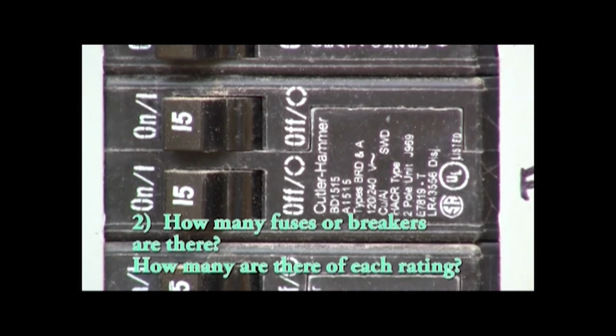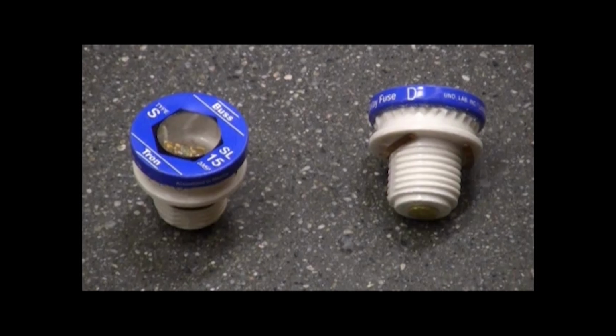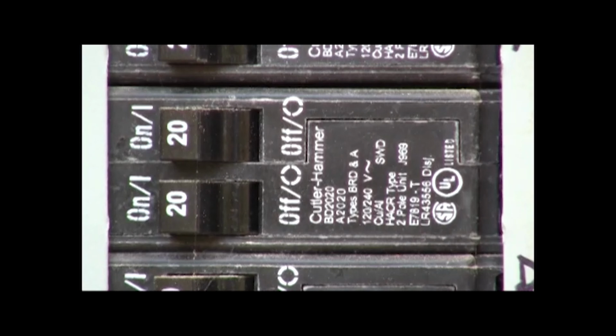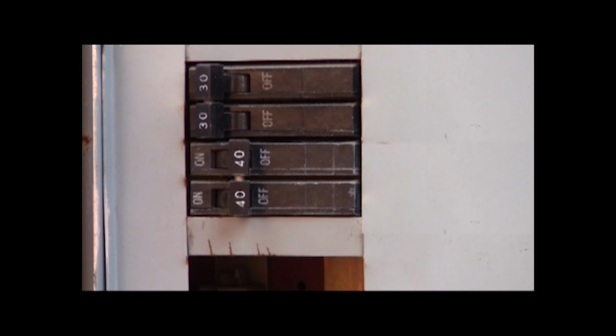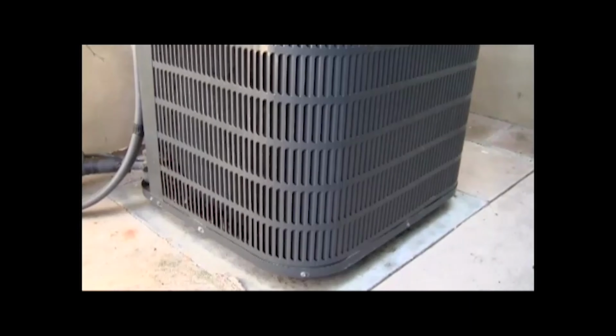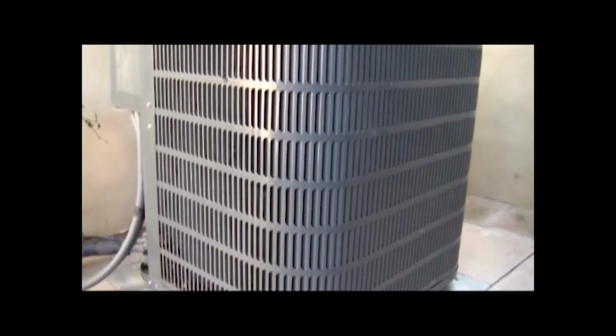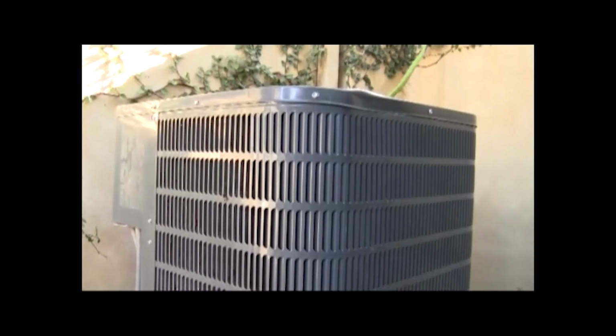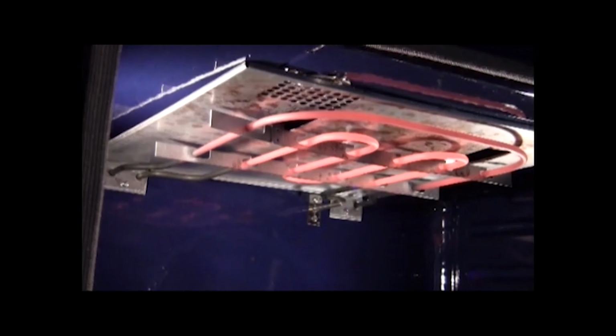Second, lighting circuits are generally 15 amp circuits. In older homes, outlet circuits too can be just 15 amps. In newer houses, outlet circuits are usually 20 amp circuits. The larger circuits - 30, 40, 50 amps - are usually 240 volts and power the major electric appliances such as air conditioning condensers, electric oven ranges, that sort of thing.